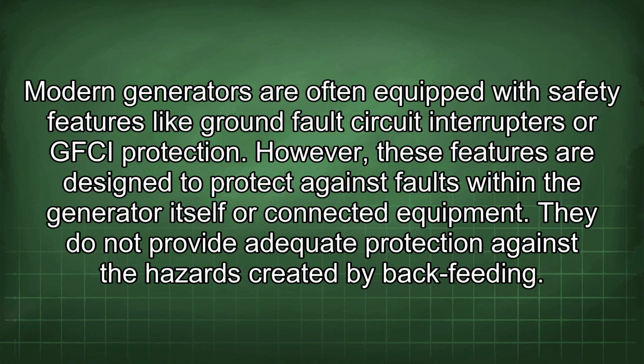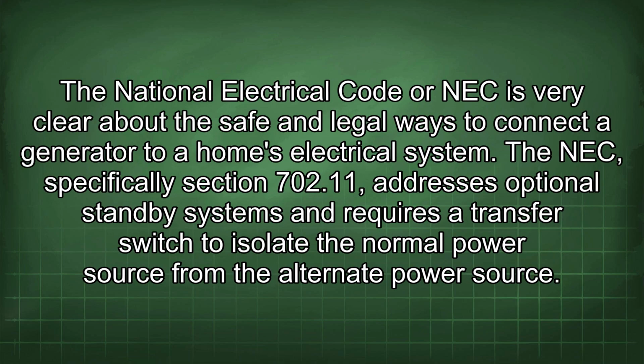Modern generators are often equipped with safety features like ground fault circuit interrupters or GFCI protection. However, these features are designed to protect against faults within the generator itself or connected equipment. They do not provide adequate protection against the hazards created by backfeeding. The National Electrical Code, or NEC, is very clear about the safe and legal ways to connect a generator to a home's electrical system.